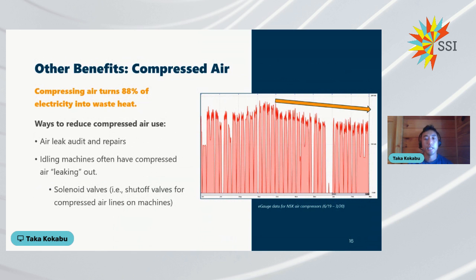So compressed air is a very expensive resource, but is common in most industrial places. A lot of times we do air leak audits and repairs to reduce that, but also idling machines often have compressed air leaking out of them, because the line doesn't know that it's not being productive. So sometimes solenoid valve installations to help shut it off, helps.